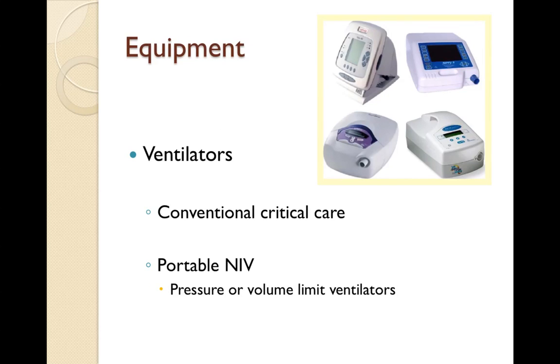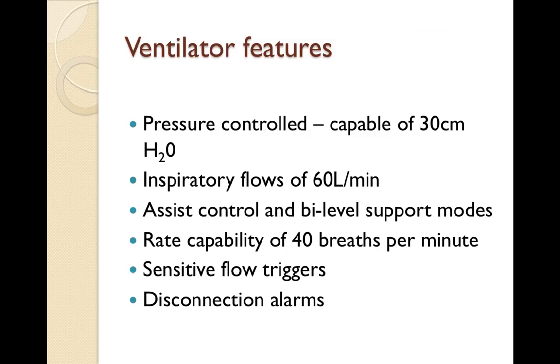Ventilators required for NIV range from ICU ventilators normally employed for intubated patients to portable freestanding devices which are either pressure or volume controlled. Portable devices are at risk of rebreathing due to single tubing. Ideal ventilator features include pressure controlled, capable of 30 centimetres of water, with inspiratory flows of 60 litres a minute, assist control and bilevel support modes, a respiratory rate capable of 40 breaths per minute, and sensitive flow triggers and disconnection alarms.